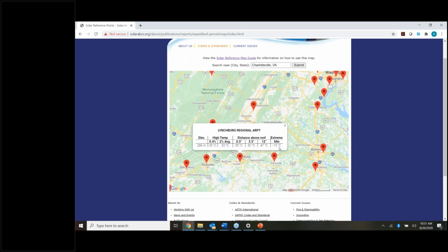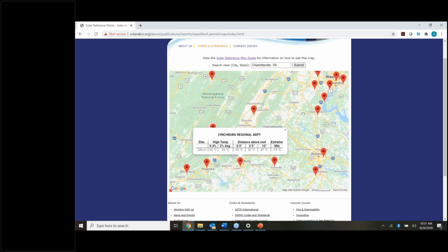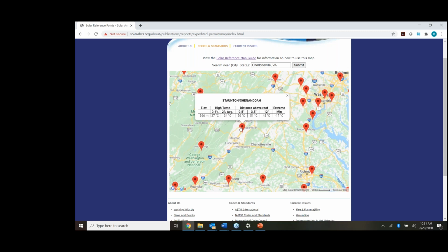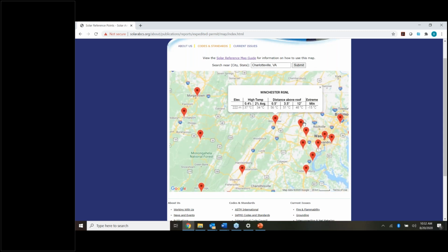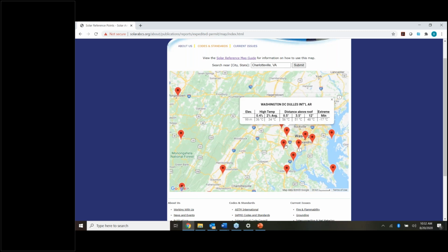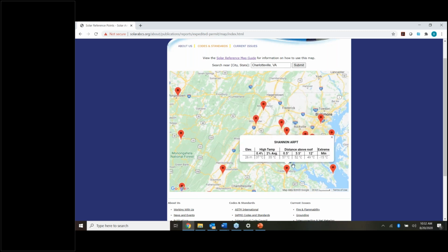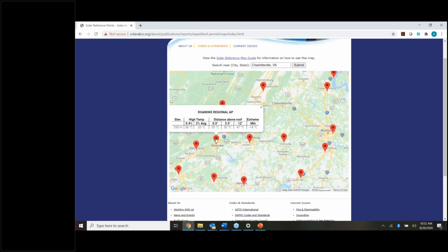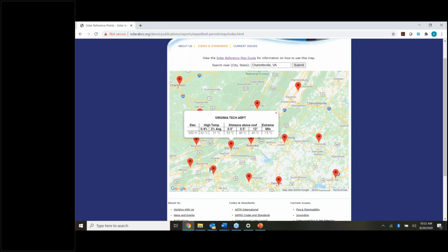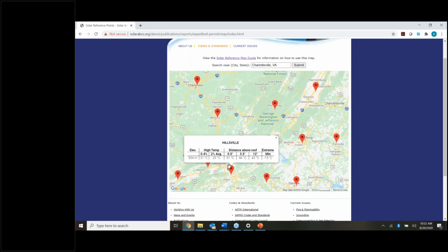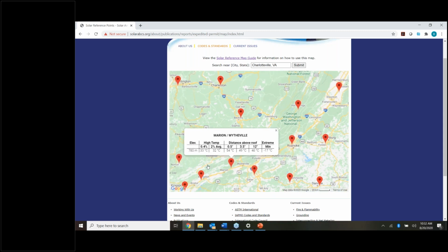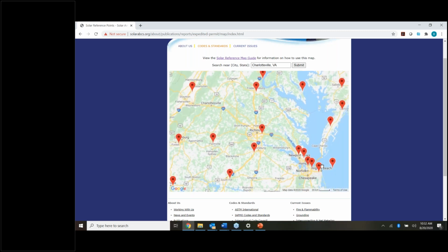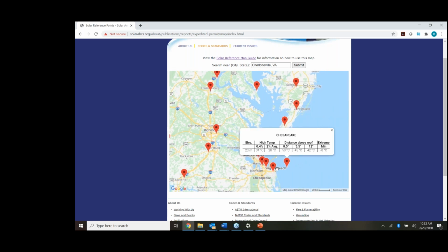Lynchburg Regional Airport. The extreme minimum is -15 degrees C. And let's go to a colder place. Let's say up here, Staunton, Shenandoah, -17, a little colder there. As you go up here, it's about the same, -15, -14, -17, -16. So you see the state of Virginia is pretty close. Now Roanoke's a little bit higher, but look at that. Not so much. Blacksburg, Hillsville. I have a friend from Hillsville, all -15s. Marion. Okay, so we're going to say that the state of Virginia is somewhere between Virginia Beach, which is -8, to about -17. That's your range.